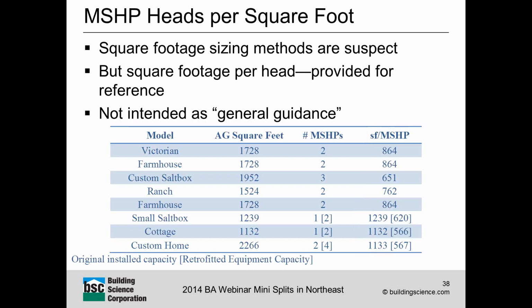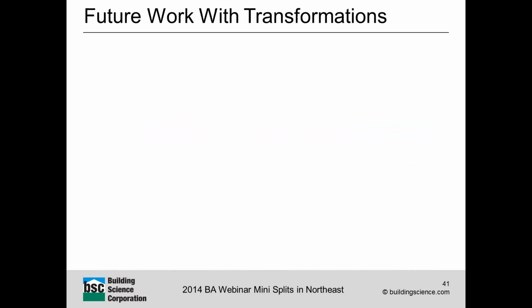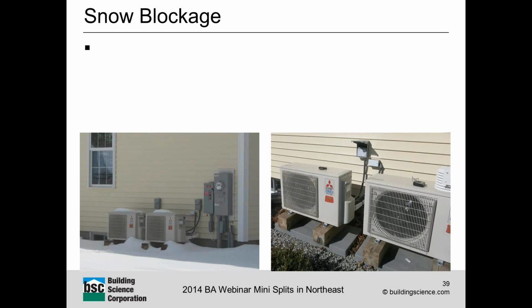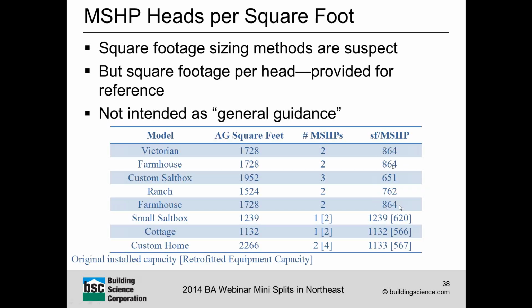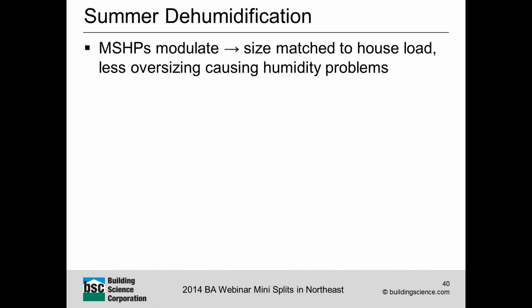Okay, I'll just go over the rest of these things and jump to my conclusions here. One thing I do want to point out is that we did calculate how many square feet per head we had. This is not meant as general sizing guidance, but it's a worthwhile bit of information. You can see that most of these houses were in the 600 to 800, 900 square feet per head. In the comfort complaint houses, we were in the 1,100 to 1,200 range. After we added that second head, we're down to the 600 range per head. So that's something to think about when you're trying to design with a system like this.